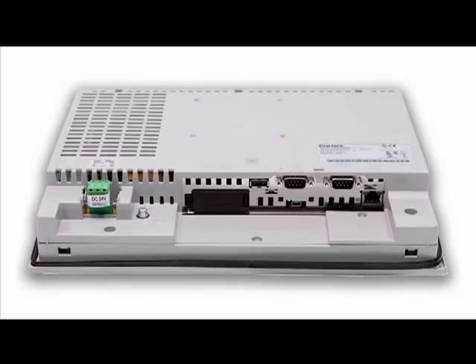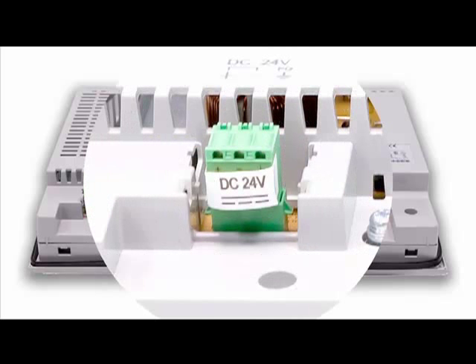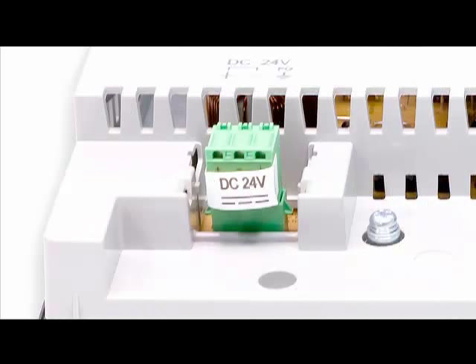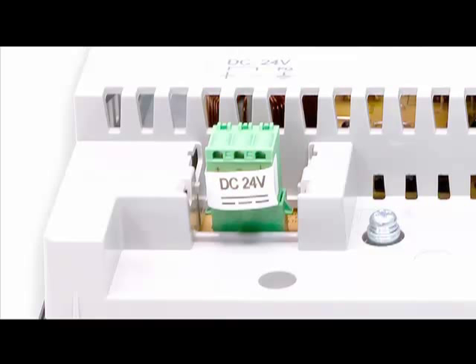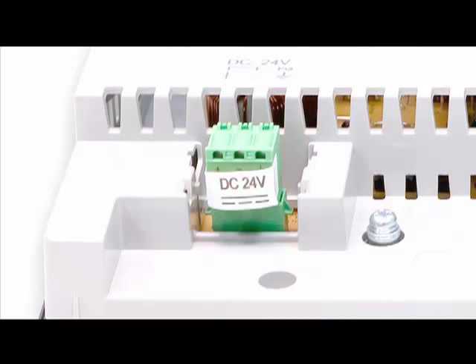This is the view from the bottom of the HMI. On the left is the power connector. Depending on the model, this can be a 24 volt DC or 100 to 240 volt AC connector. Be sure of your model's working voltage to prevent damage from an incorrect power source. The included installation guide covers the voltage ranges for the AC and DC models.